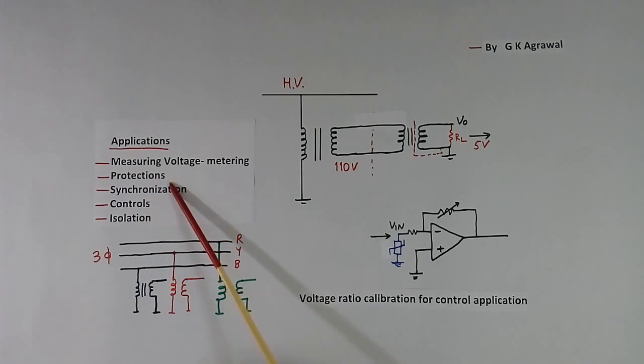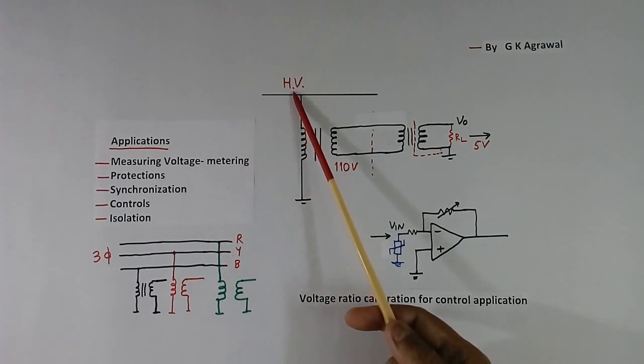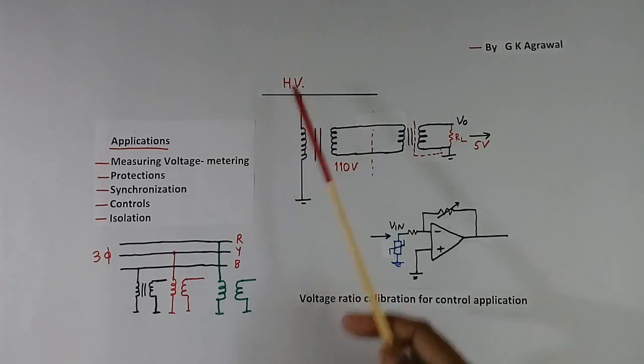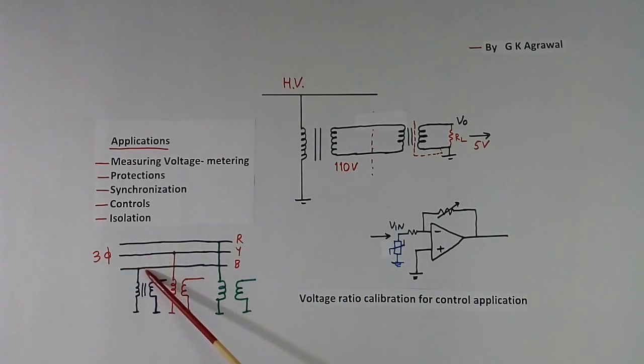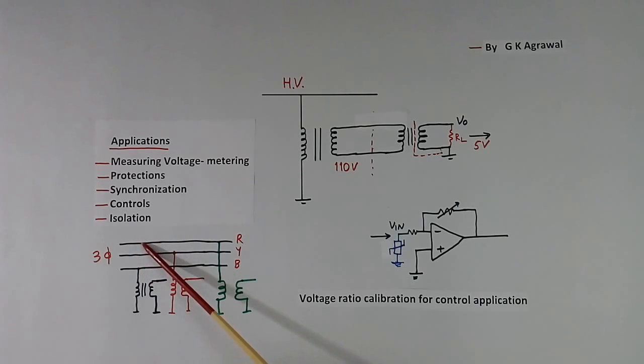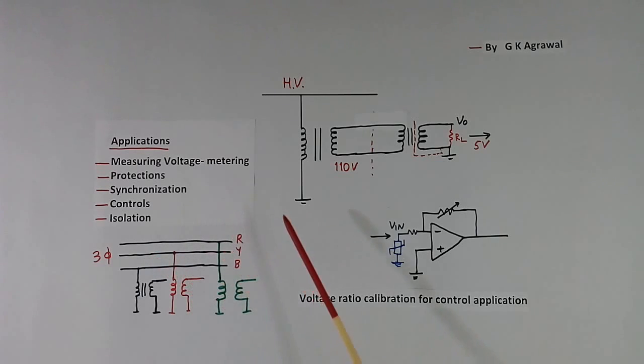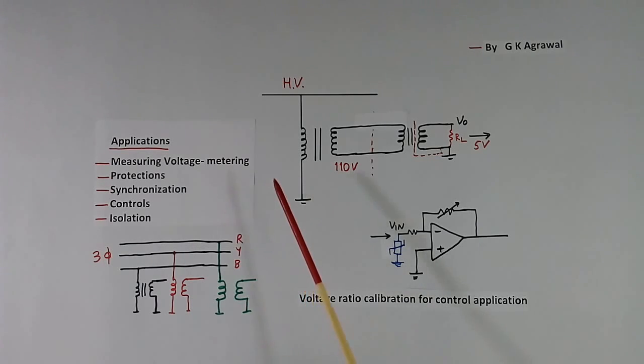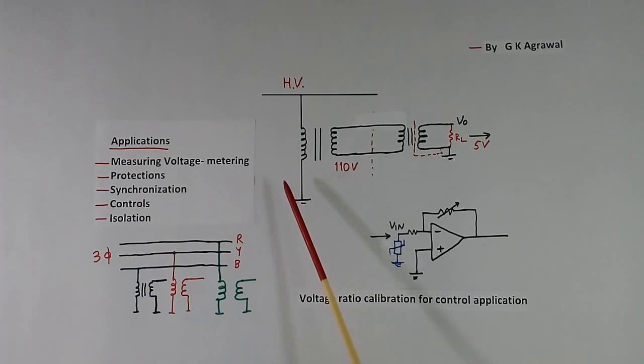Then for protection, there may be overvoltage, there may be undervoltage, and if the supply is 3-phase there may be unbalance — meaning the voltage at all 3 phases will not be equal. So we use overvoltage, undervoltage, and unbalance relays for protection purposes, and PT is required for all these relays.